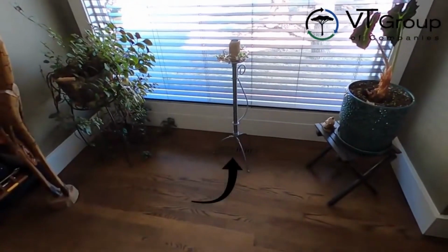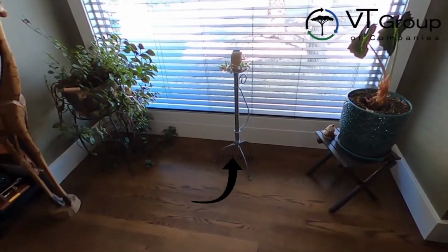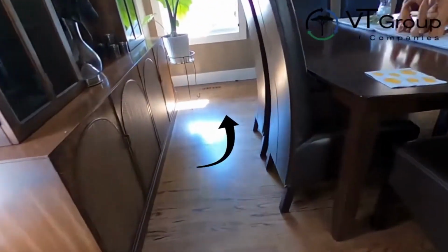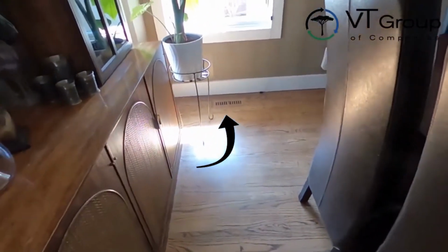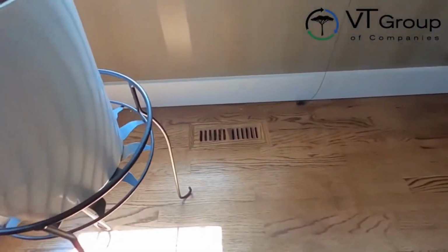And then the other thing you should be doing before we get into more expensive upgrades is considering what we call air balancing. So if we do a bit of a walk around, let's just focus on the main floor right now. At the entrance, we have a floor register in the room where we started. Behind me, just near the windows, we'll have some floor registers as well. Here we've got a floor register on that side. Obviously near the window is where we get most of our heat transfer. If we walk over, we'll have another one down here. Again, that is a supply register. If we go a little closer, you can see the supply register on the floor.